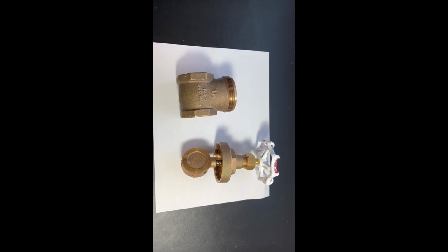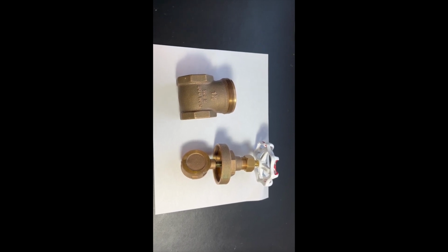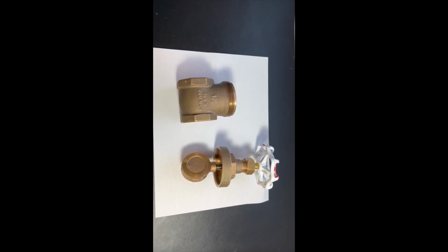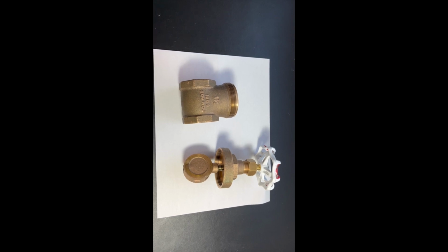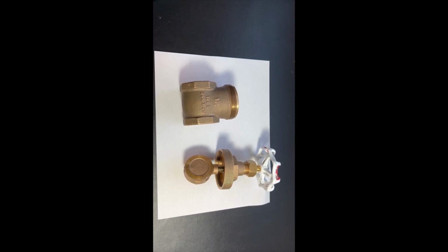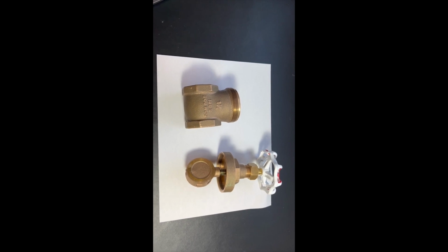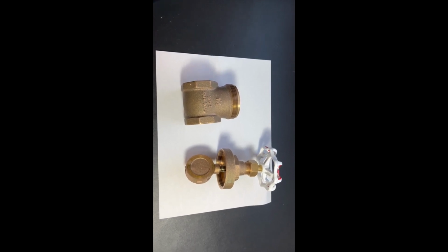The most important thing about gate valves is that they are not used for throttling or flow regulation applications. Throttling a gate valve can lead to wire draw or erosion, ultimately causing damage to the valve. Gate valves are recommended to be installed with the valve stem set in a vertical up position.